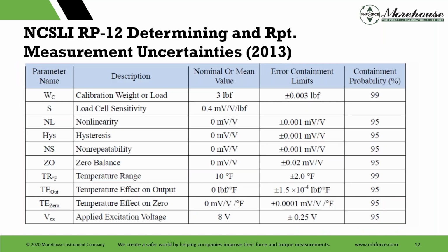And NCSLI RP12, if you go there, it's going to say something like this: calibration of rated load cell sensitivity, all this stuff. But if you have your system calibrated in accordance with one of the standards, such as 376 or ASTM E74, some of this stuff's just not needed. You'd be very wrong to put in nonlinearity and hysteresis if you're having your load cell calibrated with ascending and descending and assigning coefficients. So anyway, there's a lot here.